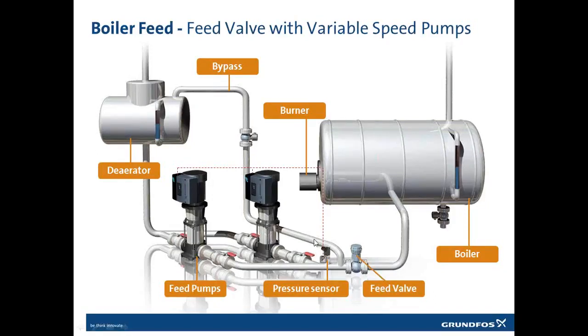We still have the bypass, ensuring that we are pumping enough water to cool down our shaft seals. But the pressure in the bypass system is now lower because we are maintaining the constant pressure in front of our feed valve.